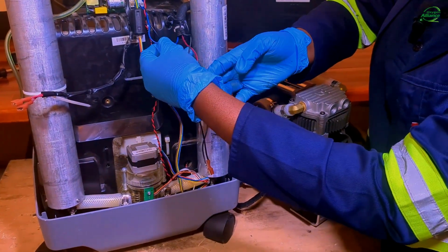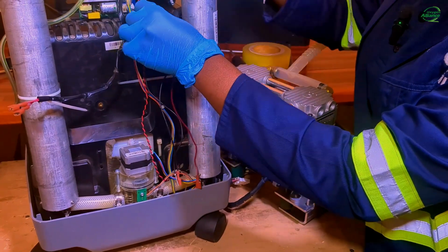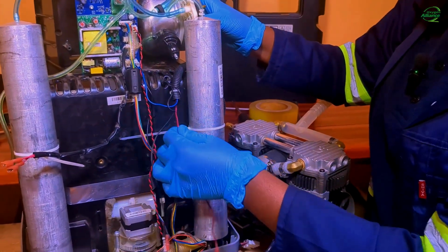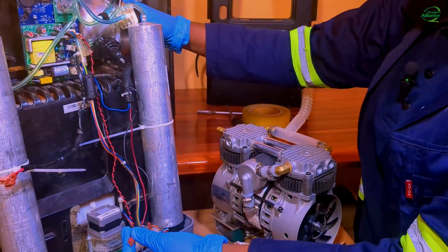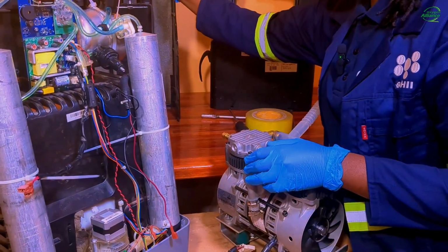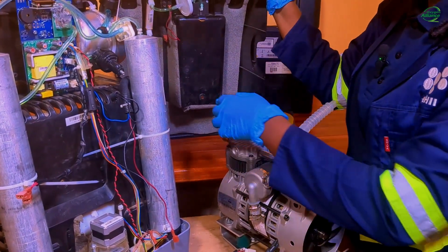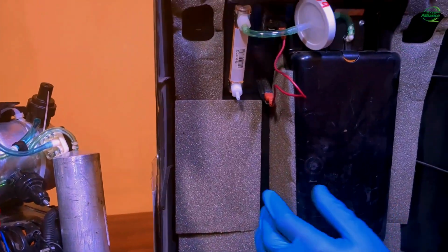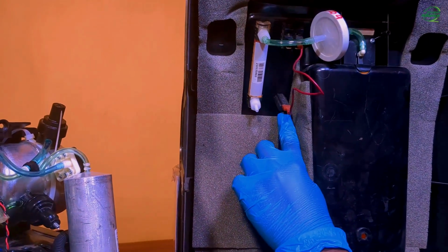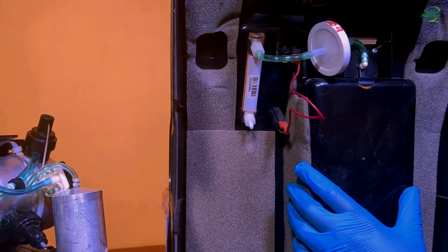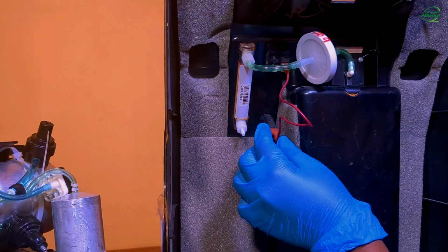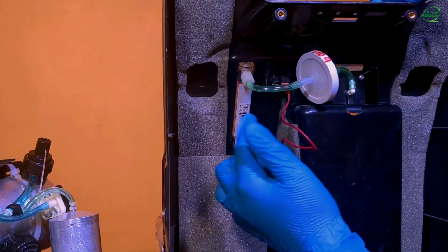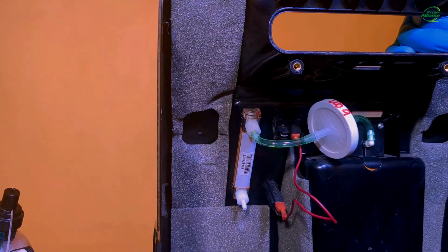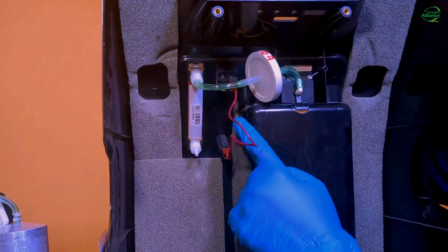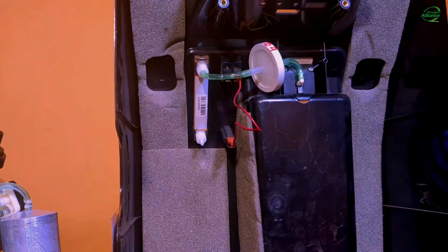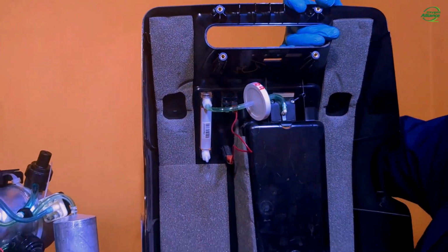So these are the two wires from behind. So the neutral wire goes straight to the board, whereas the live goes to the reset switch. So this is where it is connected. So it is connected down here at the reset switch. And from the reset switch, the power is supplied to the on and off switch. And from here is where it is connected to the control board through these cables.